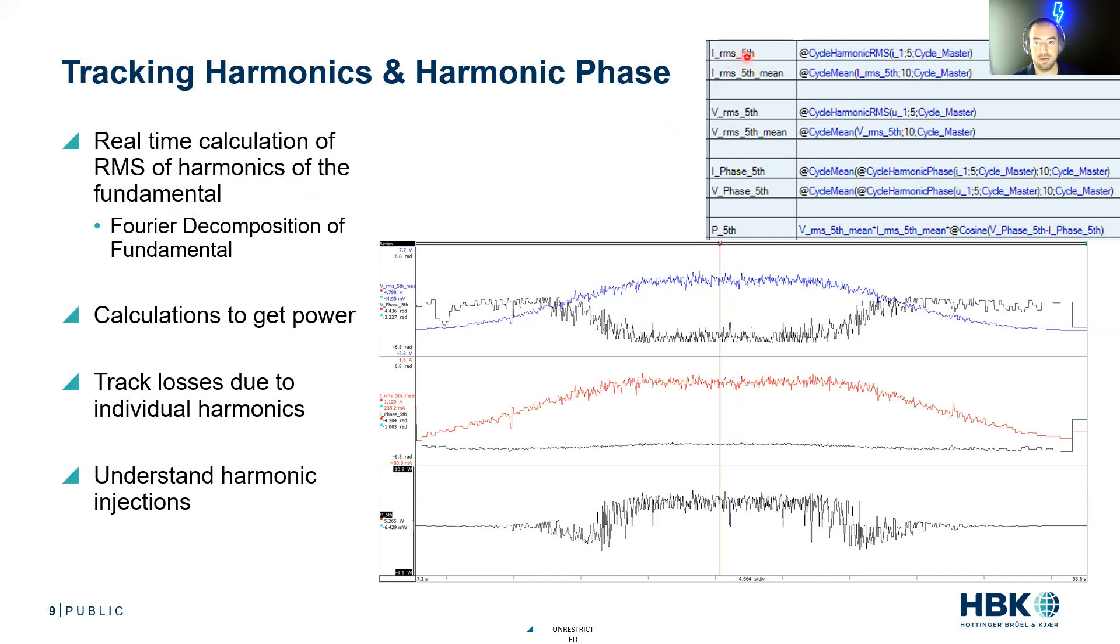We do the real time calculation of the RMS of a harmonic of the fundamental. Basically what I have up here is, I want to look at the current RMS of the fifth harmonic. We have an equation for that, and this gets executed in discrete time. I take the average of it over a period, just to get a sane rational output. So I average over 10 cycles. I take the voltage RMS of my fifth harmonic, I average that over 10 cycles - those are electrical cycles. Then I figure out the phase for both of these, because the harmonics have phase with respect to one another and with respect to the fundamental.